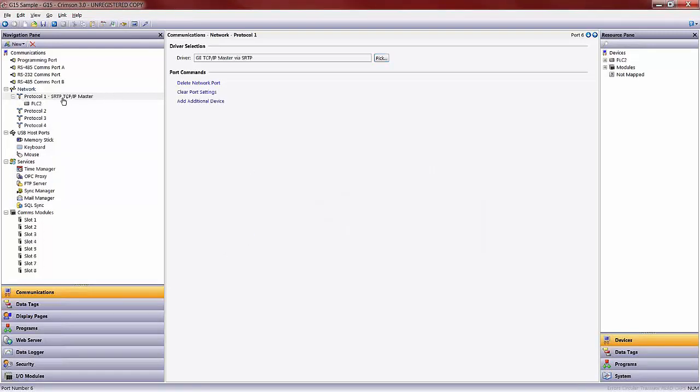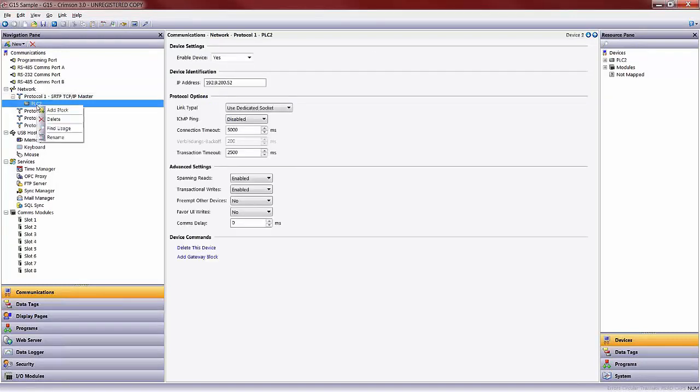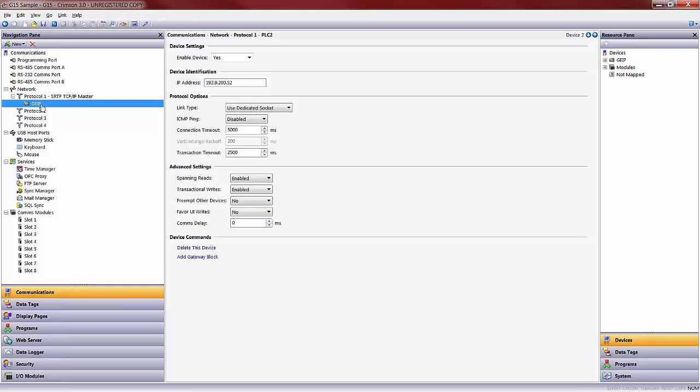Once I do that, that is the protocol associated and tied to protocol 1. You will notice that a PLC2 generically adds underneath. I can, from here, rename this, for example, to be GEIP so that I know that is my GE controller. If I click on that PLC or GEIP controller as I've renamed it, I then will go over to my device identification IP address and set this to be the IP address of that controller. As previously stated, the IP address of the GE IP controller in this example will be 192.168.1.2.